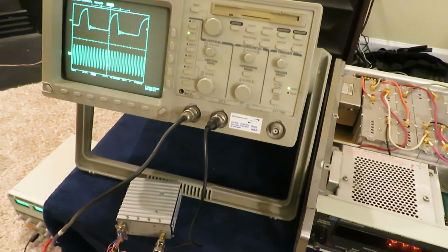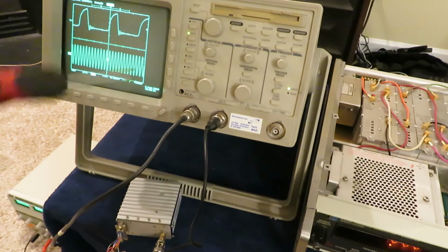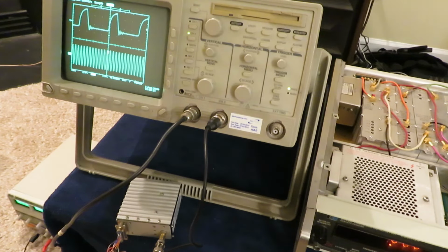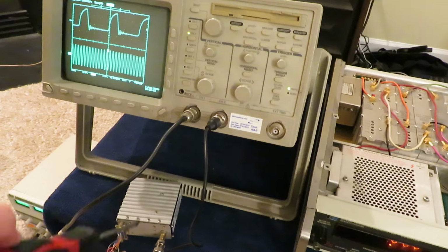But I would say for all intents and purposes, an hour or two should be probably enough to get it warmed up. So the method we're going to use to calibrate is by measuring the beat frequency of the rubidium reference against the internal 1 megahertz reference on an oscilloscope. So if you look on the back of the 8443, there is a BNC connector that says 1 megahertz reference out. You're going to connect that to channel 1 here, and the other channel you're going to connect to your reference.